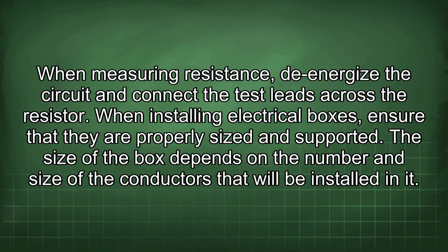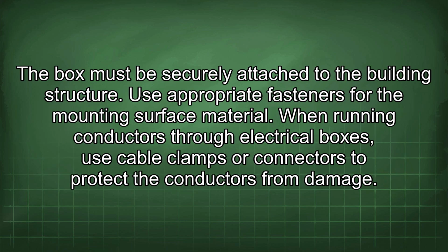When measuring resistance, de-energize the circuit and connect the test leads across the resistor. When installing electrical boxes, ensure that they are properly sized and supported. The size of the box depends on the number and size of the conductors that will be installed in it. The box must be securely attached to the building structure. Use appropriate fasteners for the mounting surface material.